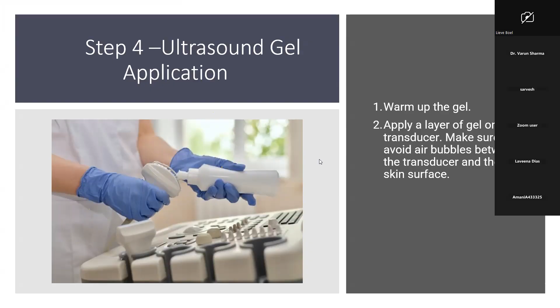So when you're applying your probe, just remember your probe is applied by just keeping it in contact with the chest. The harder you press, the more your gel dissipates, the worse your image quality. So again, this is quite important from your perspective that you apply a uniform layer of gel throughout and that you apply the probe in such a way that the gel has uniform contact. That is why linear probes are so much better. You can see a curvilinear probe in a baby is not going to have as good a contact.